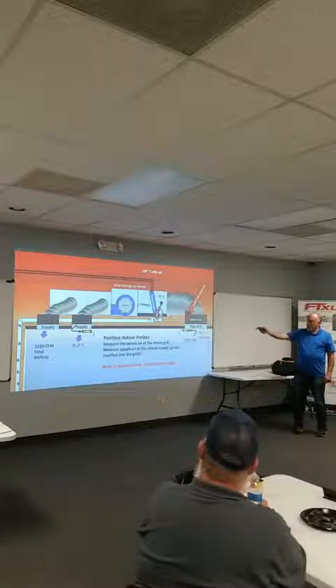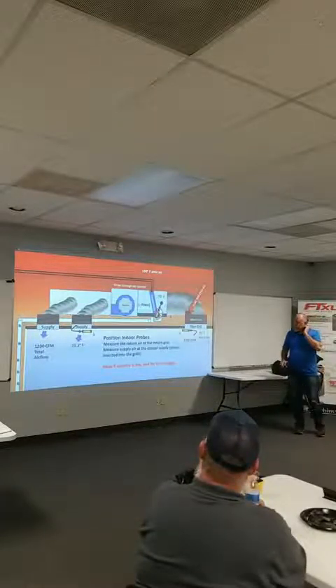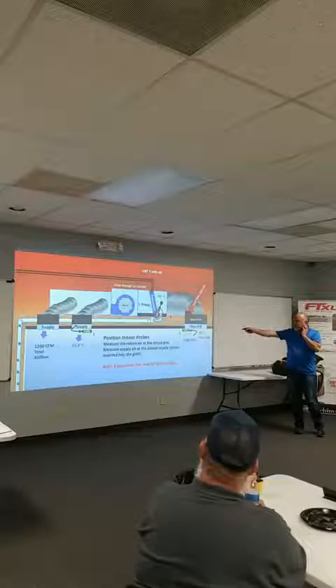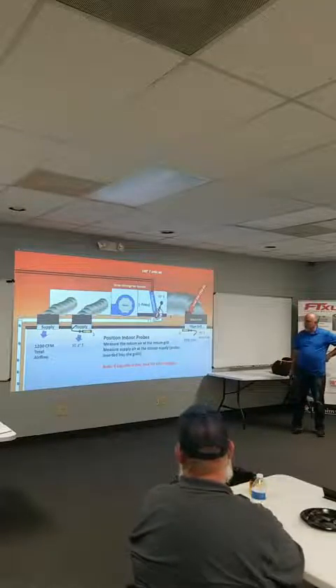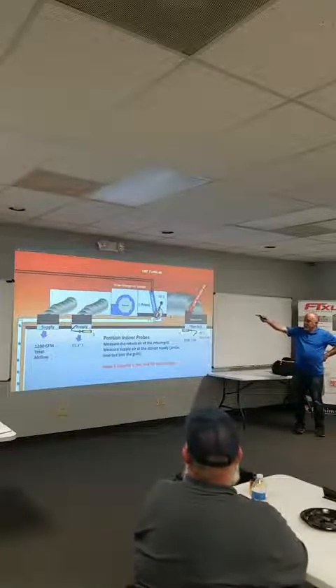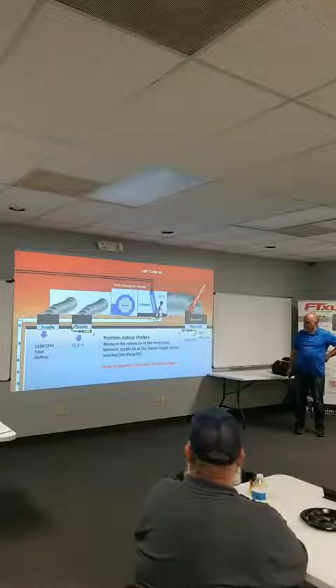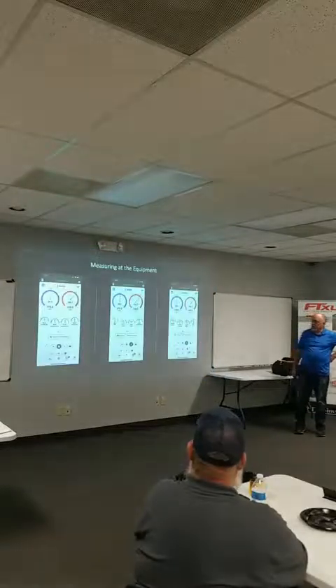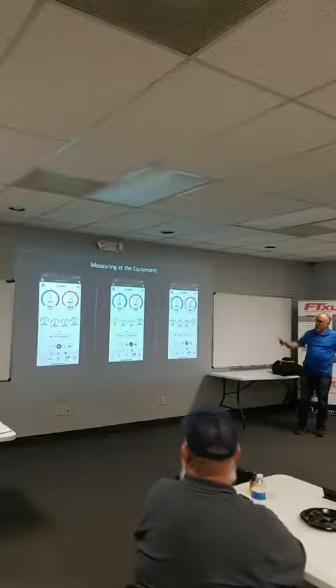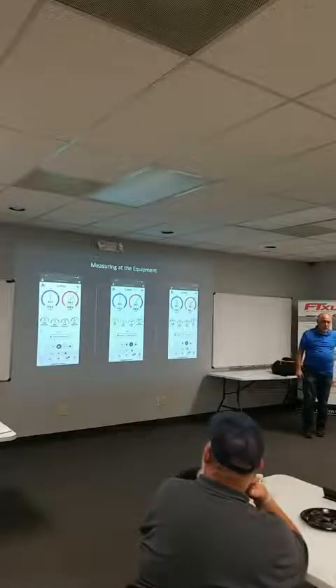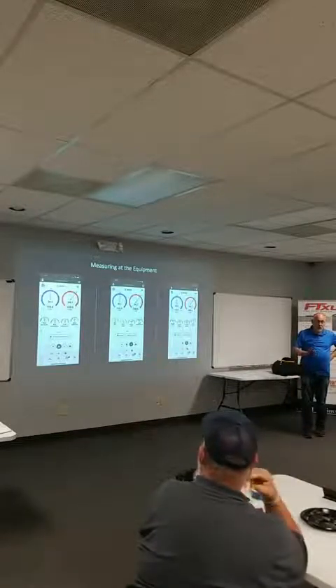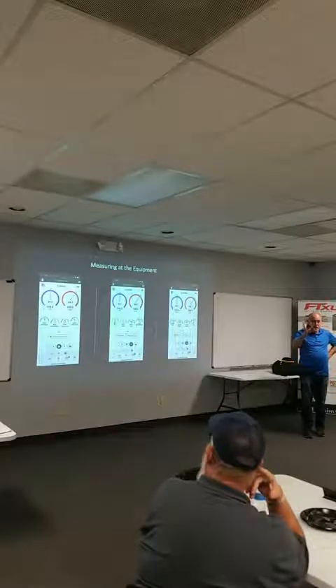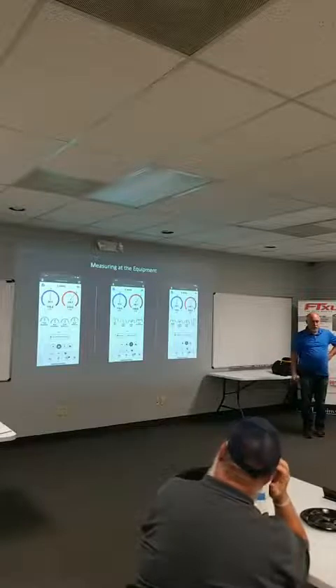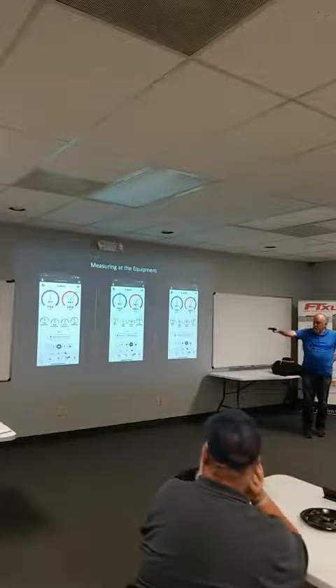If your capacity is low, here's what happens on a machine. I'm measuring 70-degree return air, got 55-degree air coming out, 75-degree air going in, though, at the mixed air temperature, right? Now, let me show you what happens here. Here's two systems. This is measured at the equipment. Okay, so all I did literally was take a probe from the return air inlet at the equipment and just move it to the grill. This is literally all we did.